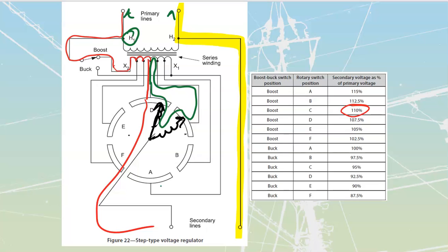They're pretty straightforward in their operation. They can be manual. They're more often than not going to be seen as being automatic. And they're going to be wicked fast. Everything inside of here is going to be a camming type of motion that's usually going to be done by a spring that's going to be wound by a motor. You'll hear these things. If you've ever been around one, you kind of just hear that whole thing tensioning down. And then when they're ready to move from position to position, it sounds like a gunshot. It's just this big, loud, metallic bang as that thing fires over and kicks over.